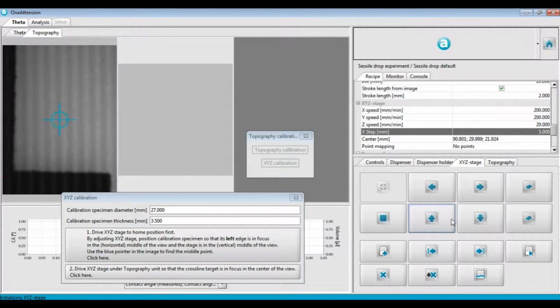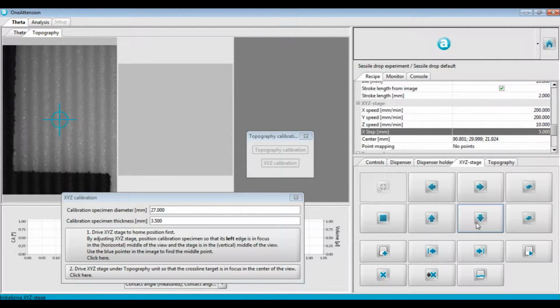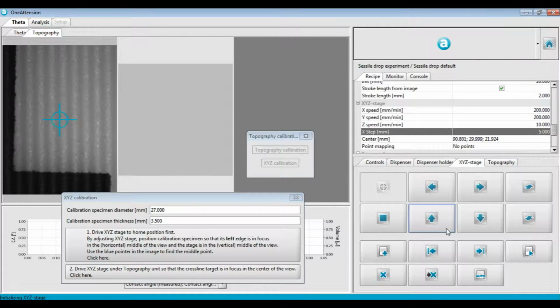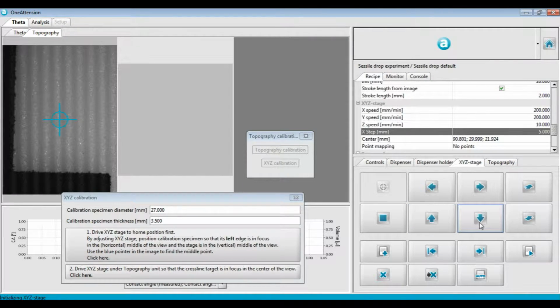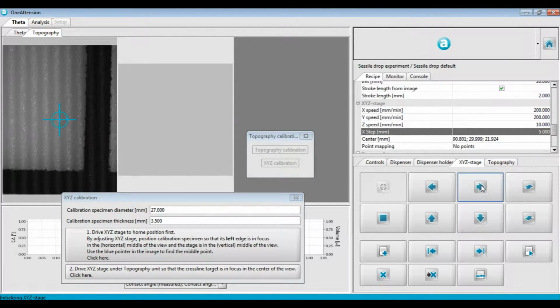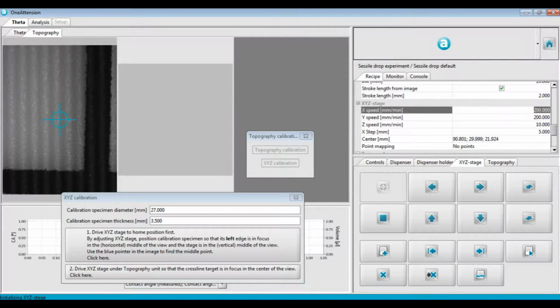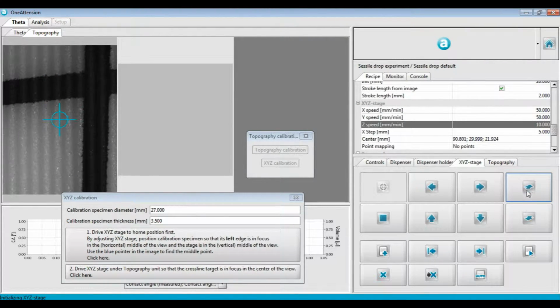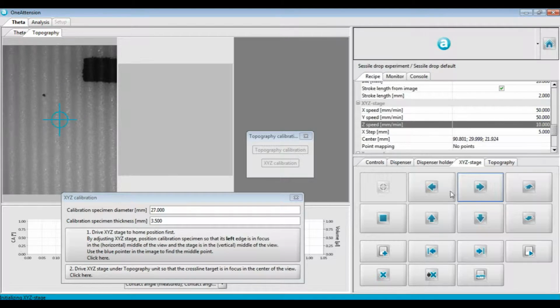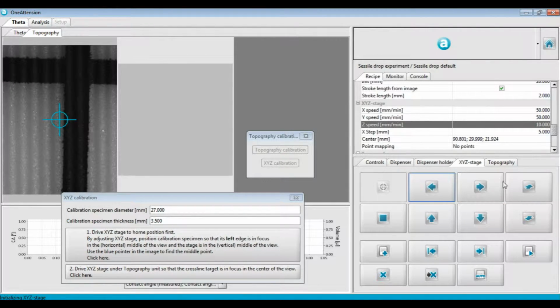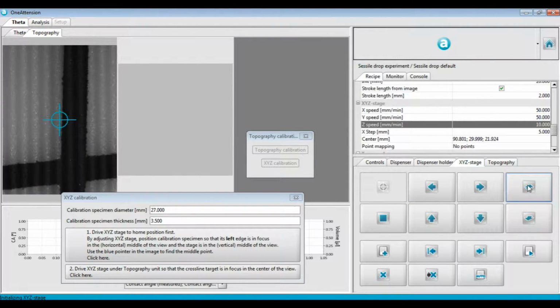Again, we can adjust the XYZ stage speeds so that we can get finer tuning of our focusing and positioning of our sample left and right. Once the sample focusing is done, we need to move the sample so that the blue crosshairs are in the center of our sample. Now there are actually major and minor hash marks on this bullseye, and so we need to use a little bit of trial and error to find the exact center of our calibration sample.